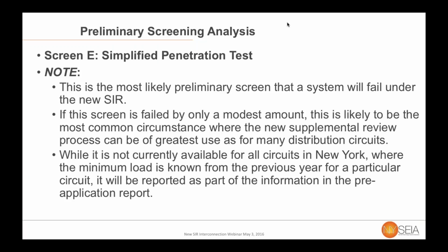While it's not currently available for all circuits, depending on which utility territory you work in, some have a large amount of data already on their circuits and can tell you what the minimum loads actually were. Others are working on methods to estimate it. If they know the circuit minimum load or have previously calculated it within the last short amount of time, this is also something that will be explicitly provided to you within that pre-app report. The pre-application report, though, only requires the utility to give data that is pre-existing. So if they don't have this data already, then it won't come back as part of the pre-application report.